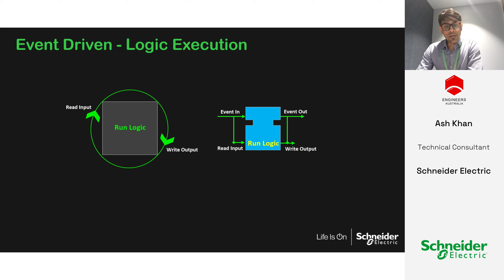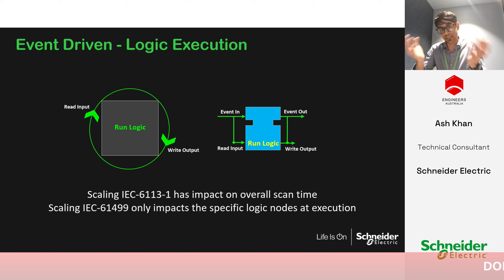As we progress forward with 61131, if we add more logic to an existing PLC, it typically will expand or extend the scan time. So it has to be revalidated every single time. So the scaling of logic itself becomes difficult. Whereas in 61499, if we were to add more logic, we typically will add it to a specific function block and it only impacts a particular logic node at the execution of that block. So it's not impacting the whole system.